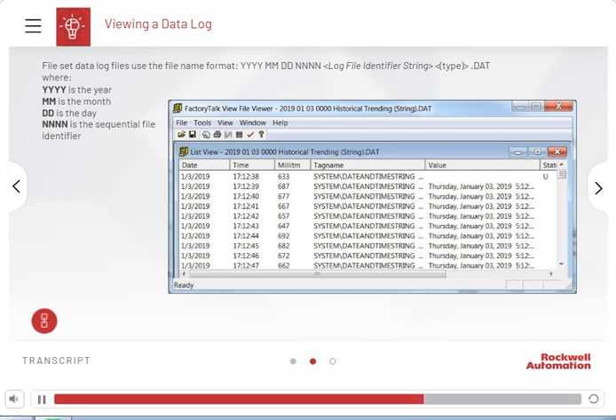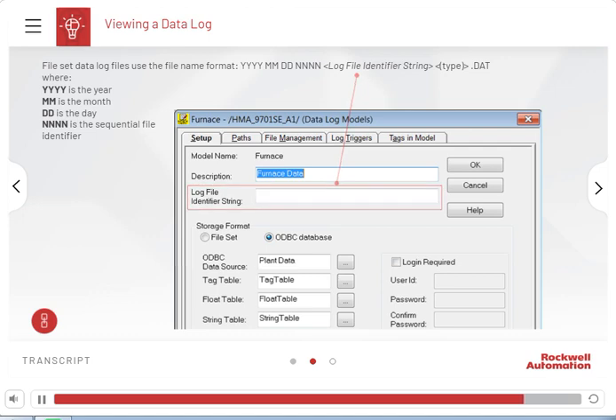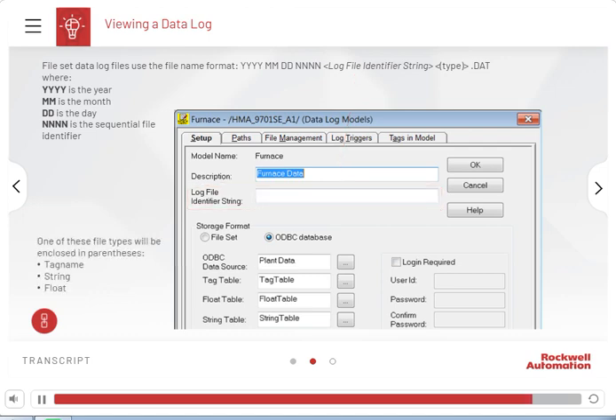The sequential file identifier indicates the sequence in which files were created. You can have up to 9,999 files per day. At midnight, the sequence starts again at 0000. The log file identifier string is specified in the Setup tab of the Data Log Model Editor. The type is the file type — one of three file types will be enclosed in parentheses: Tag Name, String, or Float.